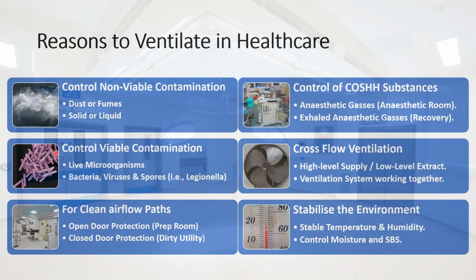The second reason is to control viable contamination, and viable contamination is things like live microorganisms, bacteria, viruses and spores, Legionella, E. coli, that type of stuff. Now, it's there to mitigate and control against these, but it can also amplify the issue. So if we have holding water in an air handling unit, and the air handling unit is blowing over the entrance of a hospital and that's got Legionella in it, then obviously it can cause an issue as well. So it's important that we keep on top of our maintenance schedules.